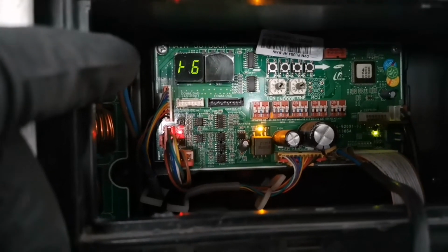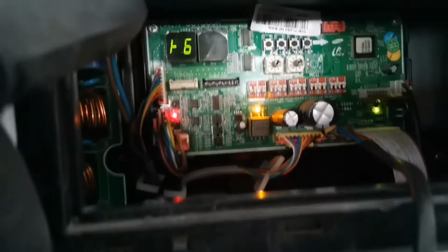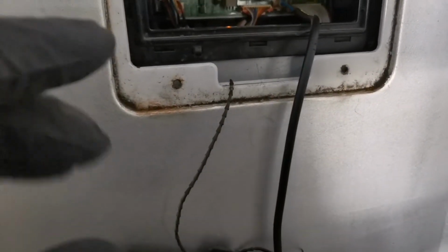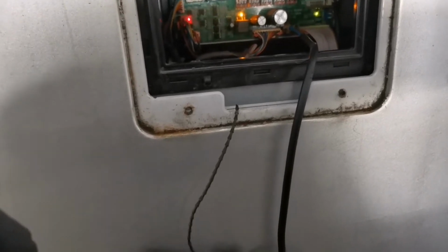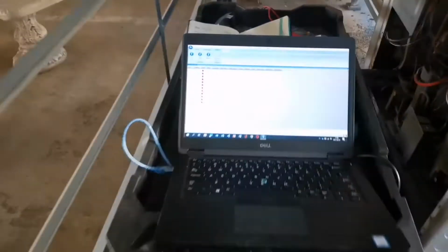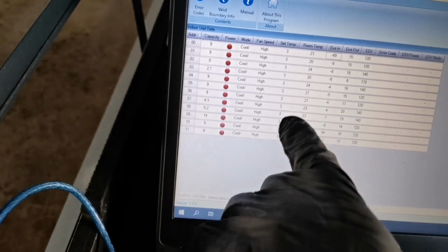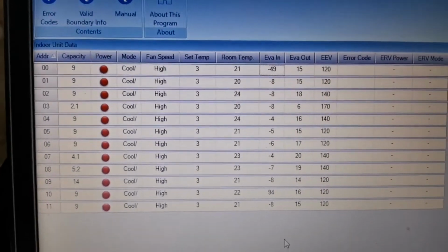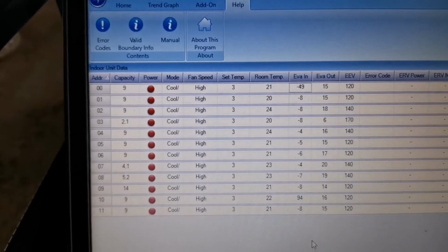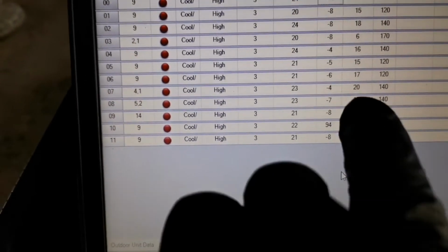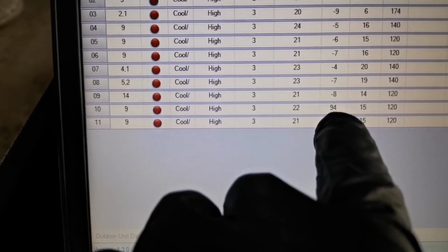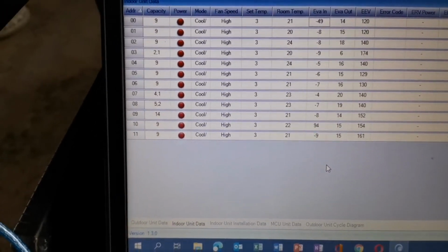Alright, so the system right here, we got it in cooling operation right now, forced cooling operation, so it's a test mode. This will help us to start the system on full load, so it will disregard the wired controllers downstairs. And if we come over here, you'll actually see that the set point is on 3 degrees on all of the units. But what's interesting is, look at this one right here, our evaporator in temperature on the address 00 is minus 49 degrees Celsius. And as we go down, this is the other one that jumps at me real bad, is 94 degrees on address 10.